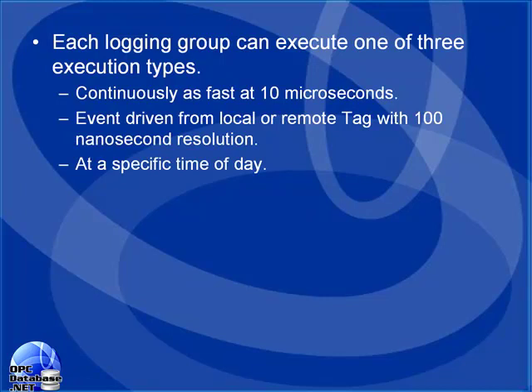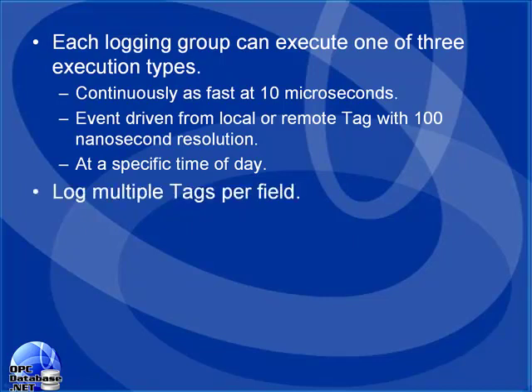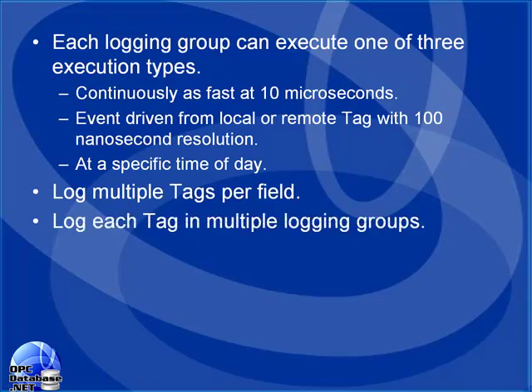You can log data as fast as 10 milliseconds continuously. With event-driven logging, we can maintain up to 100 nanosecond resolution. You can also log data at a specific time of day. This is great for daily production reports. We can log multiple tags per field and log each tag in multiple groups.